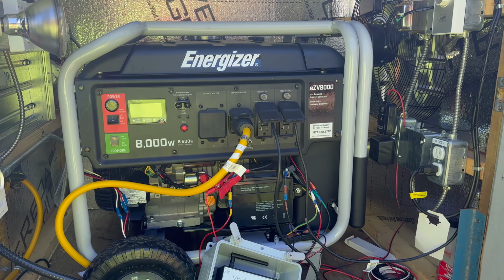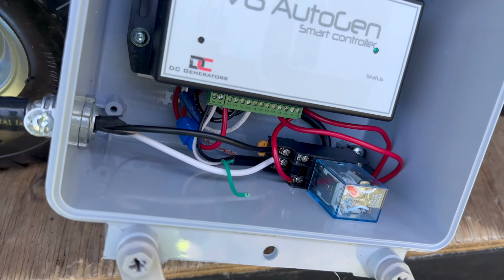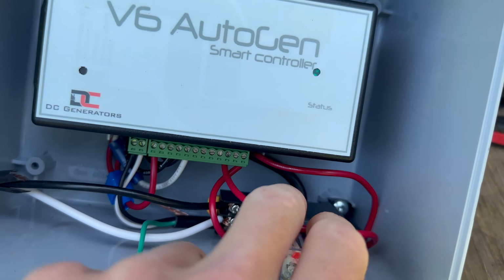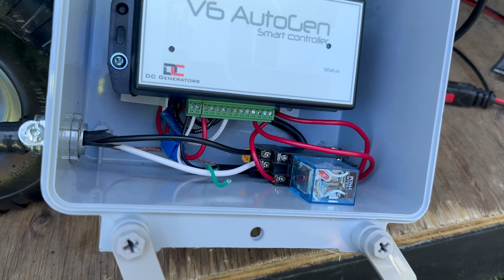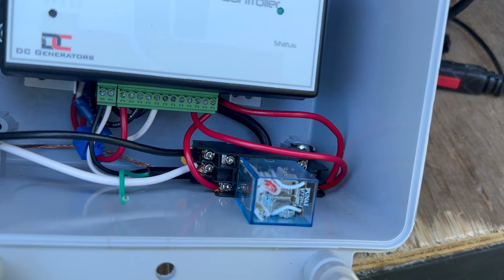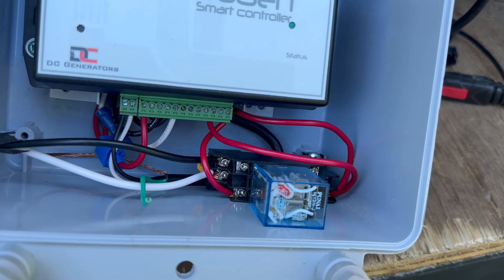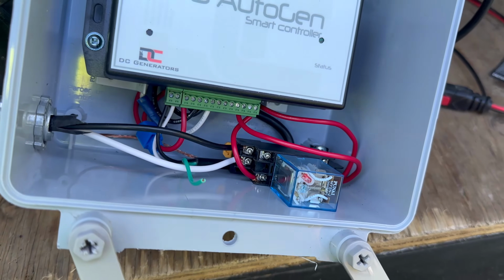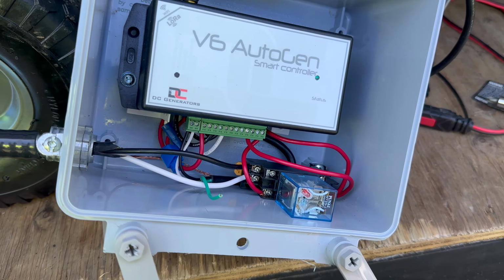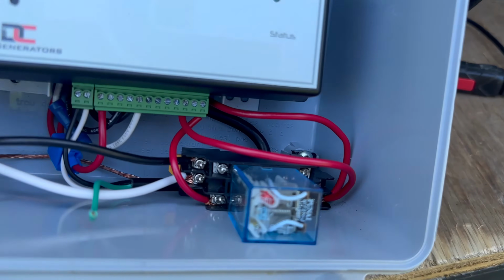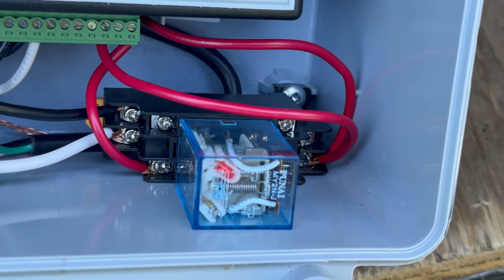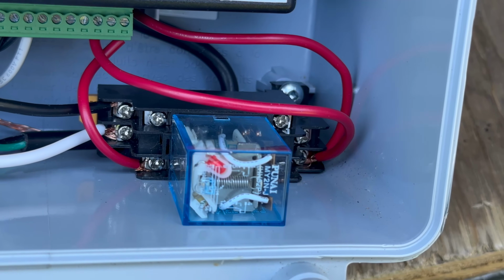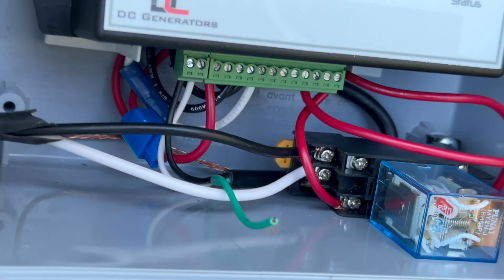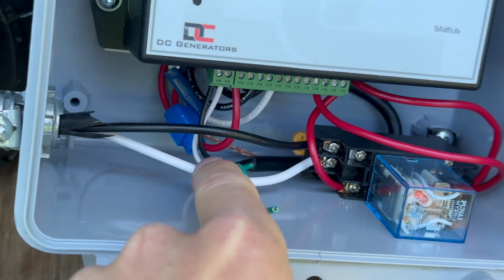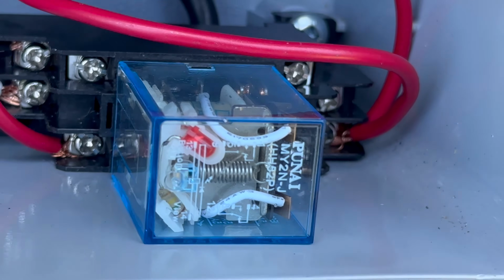But then how does this actually know when the generator needs to start? That is done with these connections right here, pin 10 and pin 12. Those are configured so that when they receive 12 volts, the generator will start. Since they're just receiving voltage from the same battery that supplies the thing, without this relay, they would constantly be receiving 12 volts, which would basically always be telling the generator to start, which wouldn't work. So they need to be run through this relay. This is another 120 volt coil relay, and I am switching 12 volts with it. The 120 volts comes in right here, which is active right now. It's currently receiving 120 volts, that's why this little red light is on.